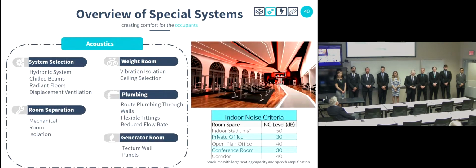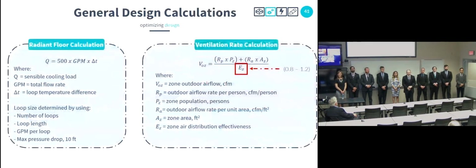To ensure a high quality of acoustic performance for the space, the systems that we chose were traditionally low noise generating. The chilled beam units and the displacement ventilation diffusers were sized to have NC levels no higher than 25. The main mechanical room and the AHU rooms were also decoupled from the main structure, and the equipment inside uses vibration isolating techniques, including equipment pads, spring isolators, and flexible connections. Here are shown some of the design calculations we used. On the right is the ventilation calculation taken from ASHRAE 62.1. As Danielle said, we used displacement ventilation, and so we're able to increase the EZ value to 1.2, which reduced the total amount of outdoor air we had to bring into the facility.